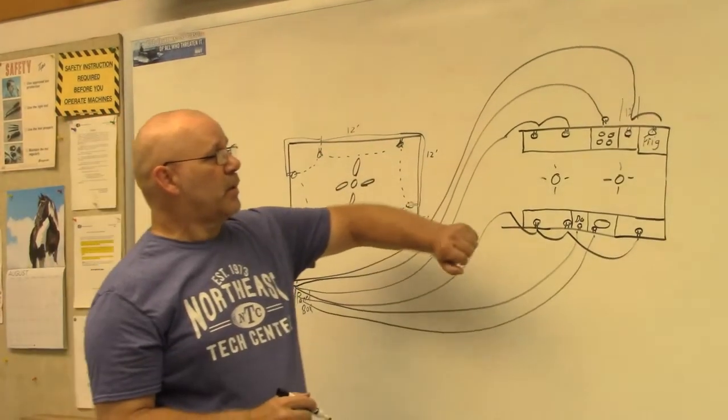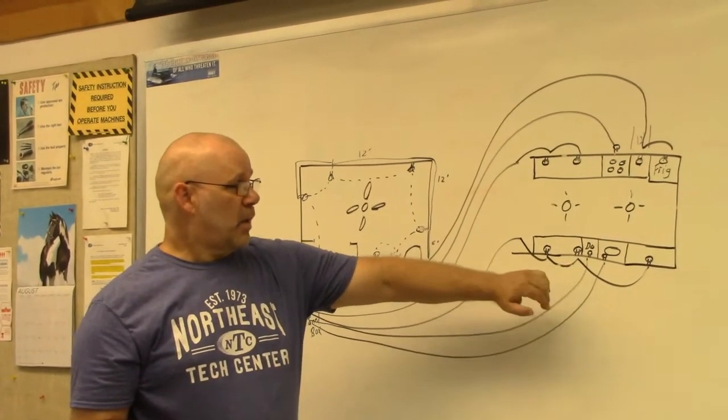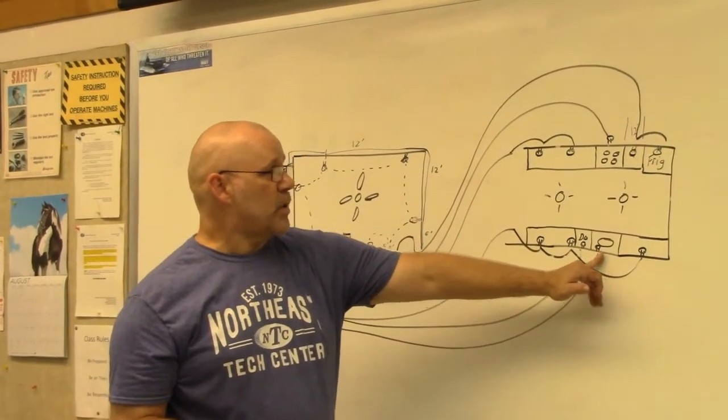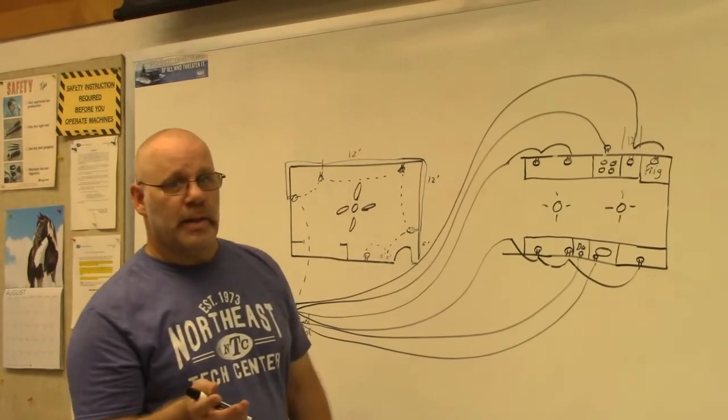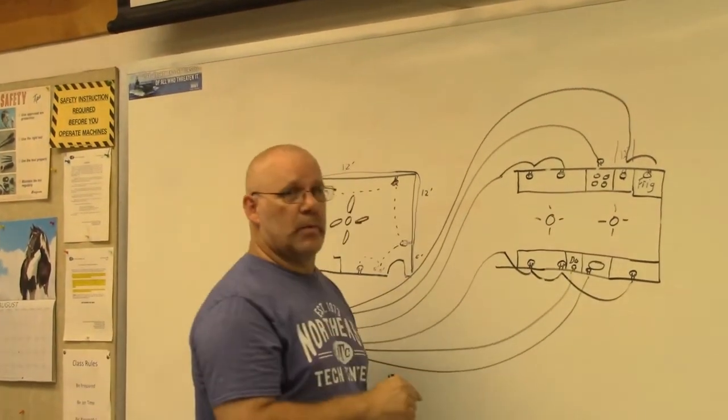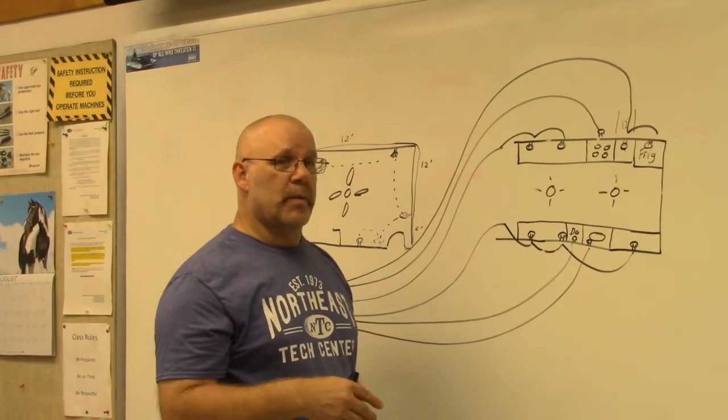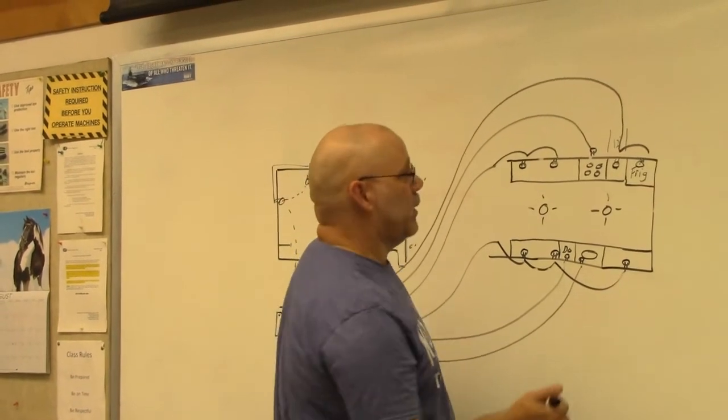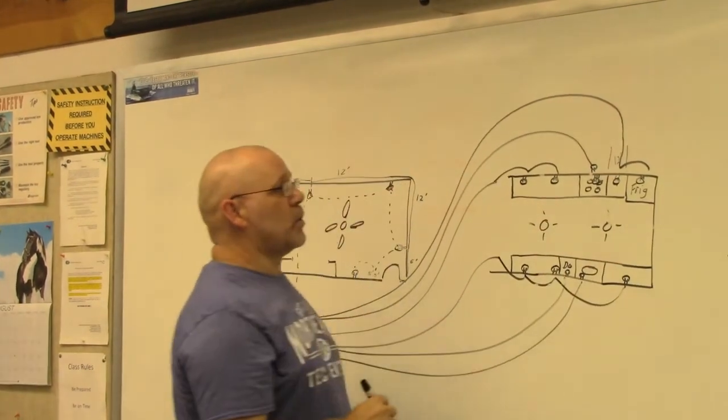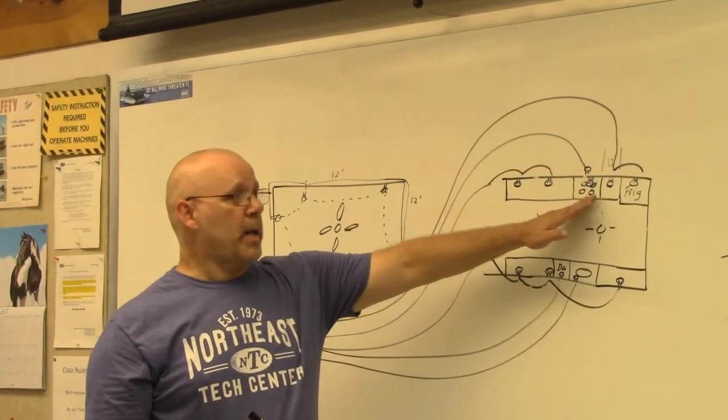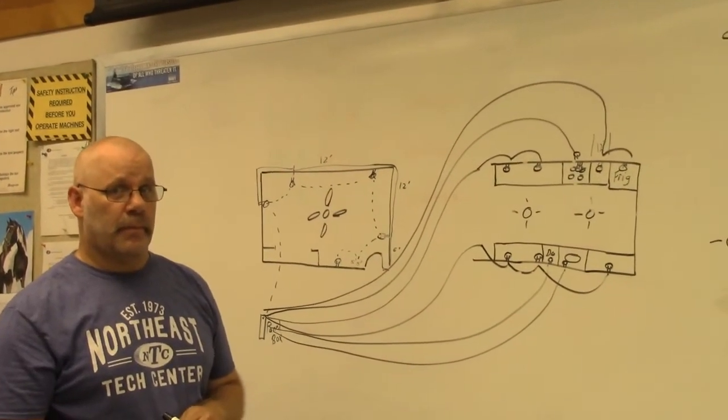So in the circuit, in the kitchen, I've got one, two, three plug outlets, circuits. I've got dedicated for the dishwasher, dedicated for the disposal, dedicated for the microwave. What else do I need in there? Well, I need something to run the stove. If it's a gas stove, it's going to get a 120 volt outlet. If it's an electric stove, it's going to get a 220 outlet. So let's say this one's going to be electric. So then I would need to put the 220 volt symbol behind the range, so that we know that it's going to be a 220 volt circuit.